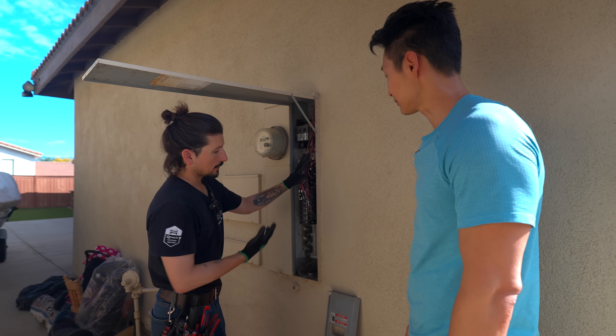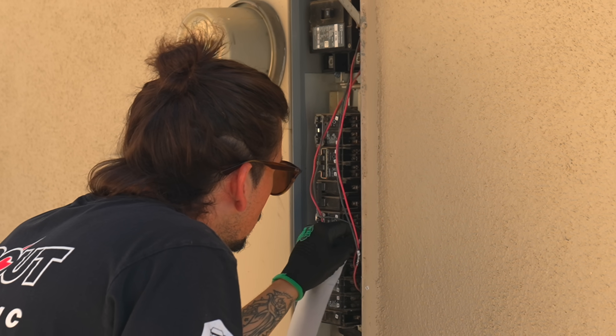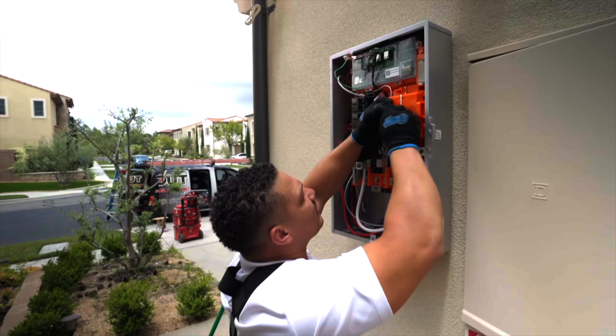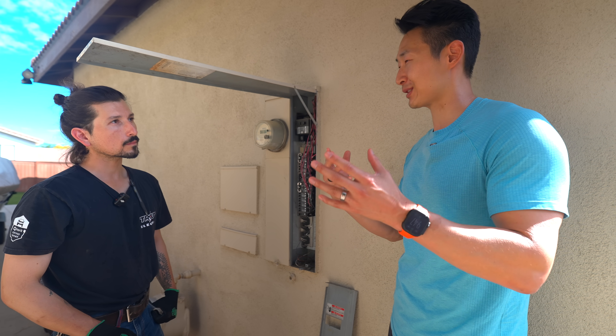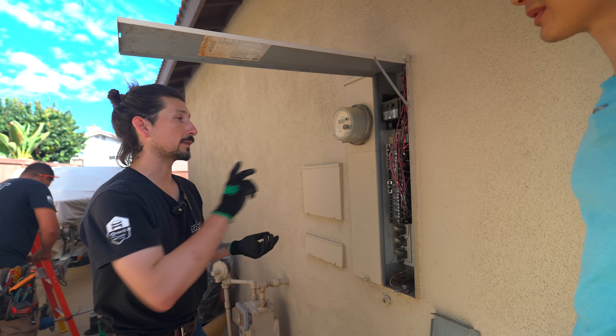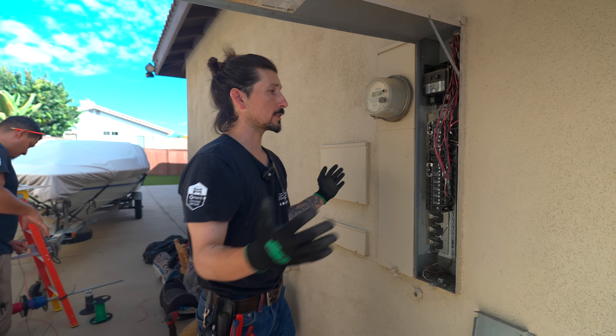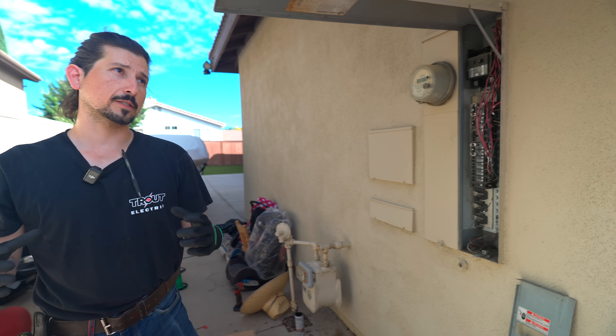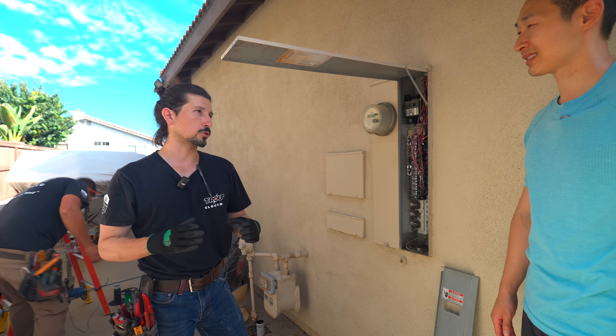One of the things we look for is damaged wiring and signs of overheating. As long as we have good wiring at the panel, no overheating, no damage, and the panel's not damaged, then generally we're good to install — as long as we size the system appropriately. With the Cybertruck PowerShare installation it's critical home loads only, but with EcoFlow you have this huge sub-panel with so many breakers. The choice of whole home backup versus critical load really depends on your backup goals — this system is scalable.